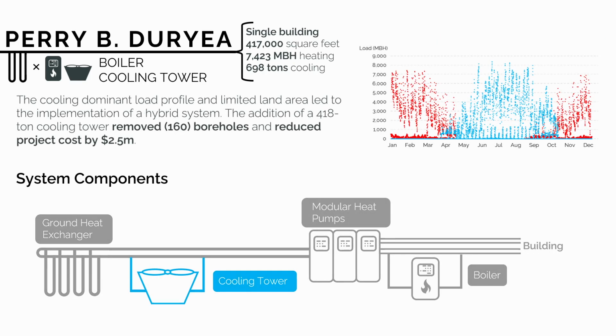When we looked at the loads, shown at the top right, you can see how much higher the cooling loads are compared to the heating loads. We realized right away the system would be cooling dominant. So of the 700 tons, we installed a 420-ton cooling tower, which removed 160 boreholes and reduced project cost by $2.5 million.